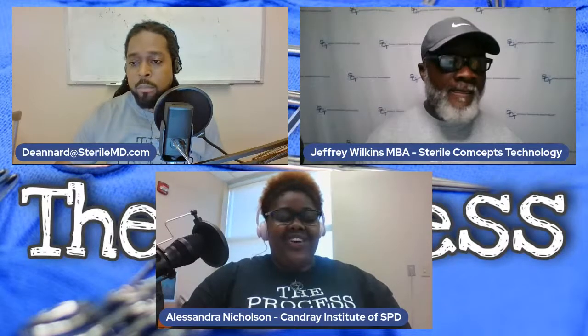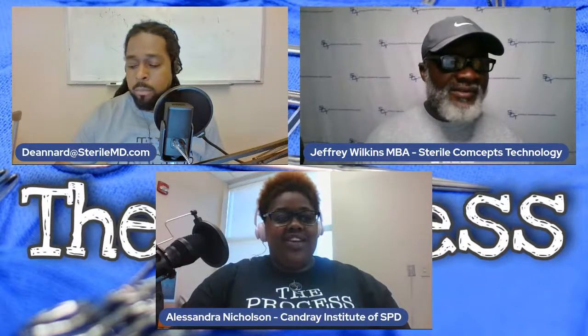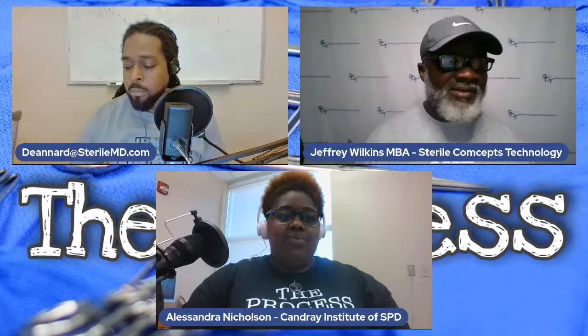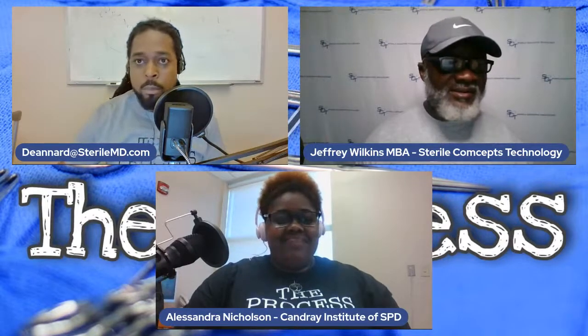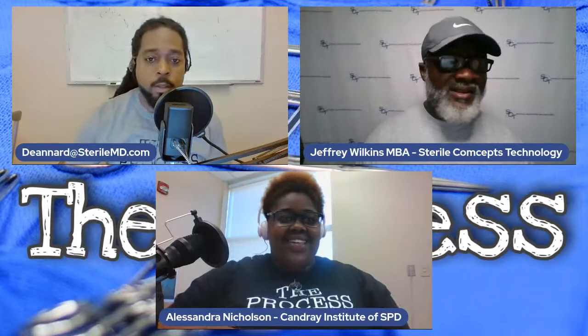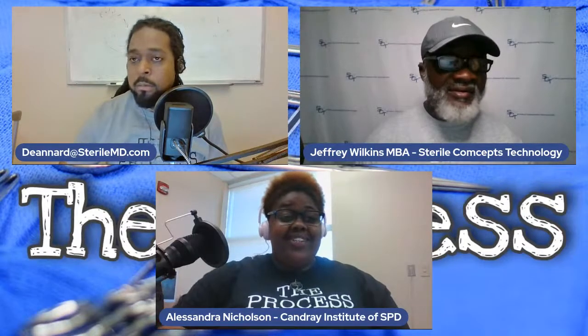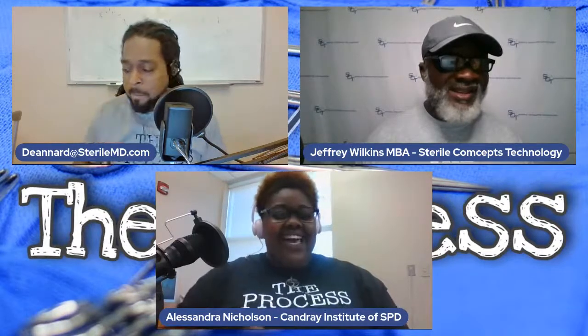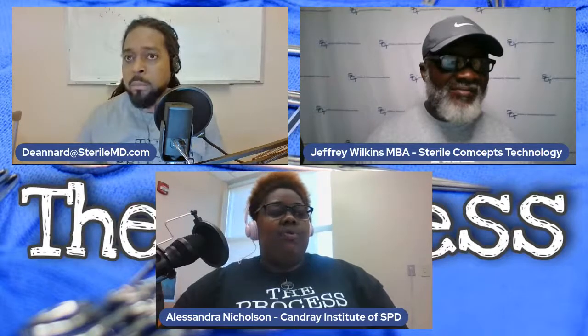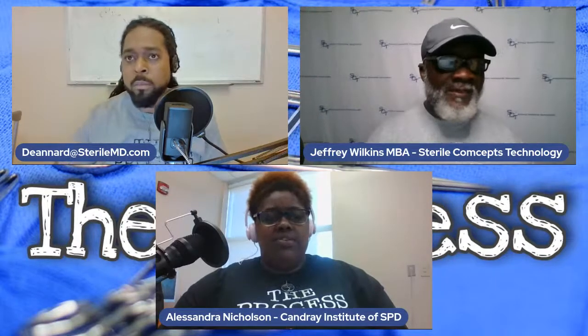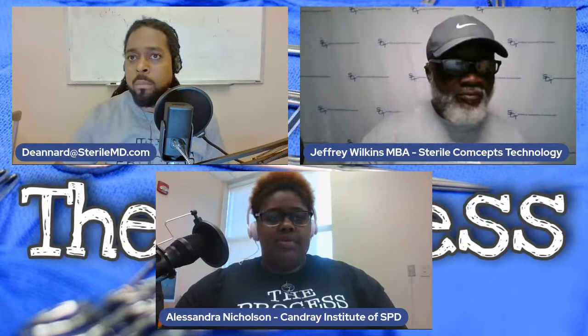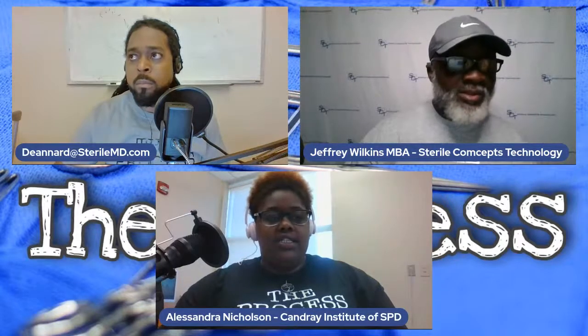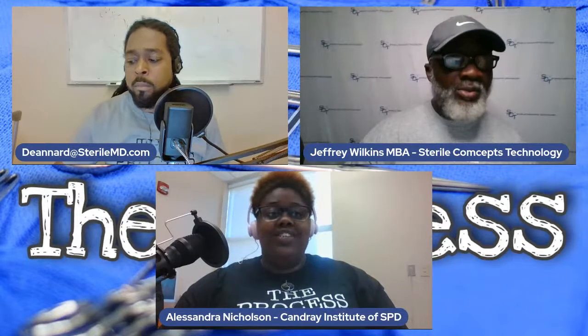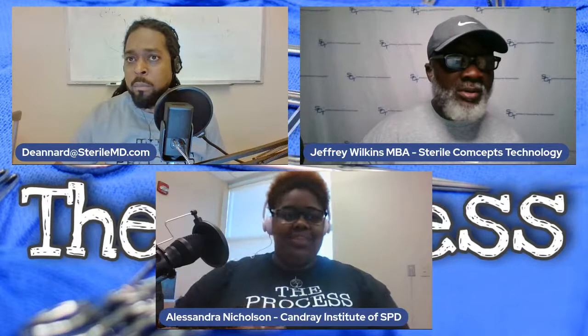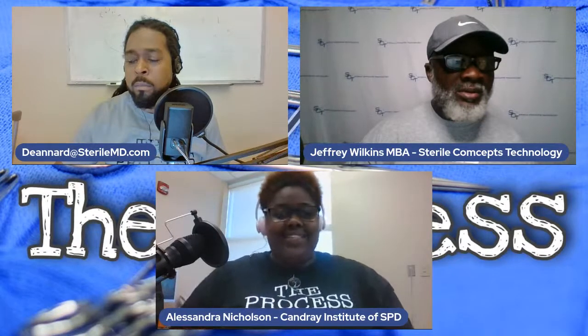I had an interesting conversation with some Da Vinci educators over their new Ion probe. Have y'all seen this thing? I have not seen it yet. Oh well, SPD Nation, look that up. Da Vinci has a new probe that's similar to a scope, is my understanding, but it's like 1.3 millimeters in diameter and it's insulated interiorly and exteriorly. So you actually have to do a conductivity test where you dip the thing in the water. You're like a mad scientist, basically.